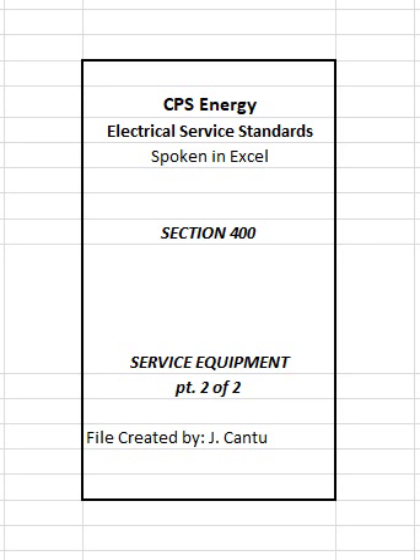408.2 Sealing of meter disconnects. Meter disconnects ahead of 480Y/277 volt self-contained meters shall be sealed by CPS Energy to the extent necessary to protect unmetered conductors. Personnel requiring access to the interior of the meter disconnect switch shall first notify CPS Energy.